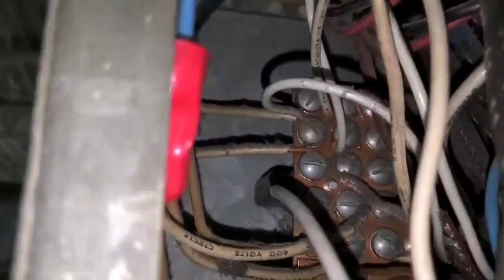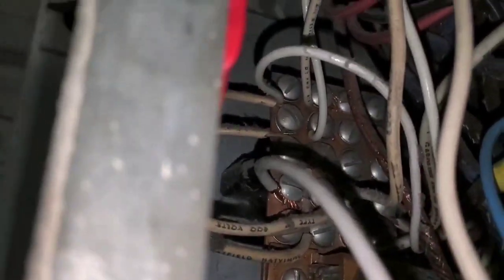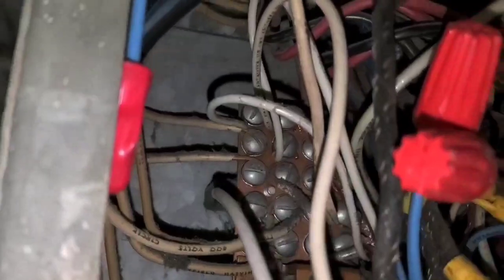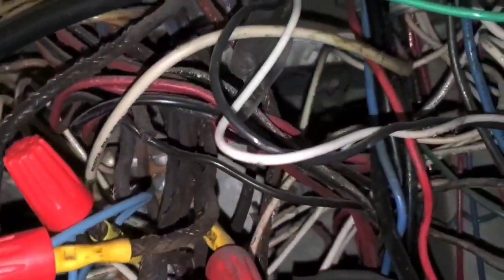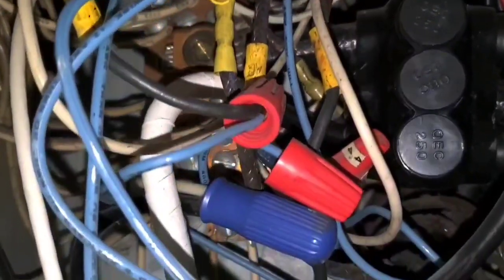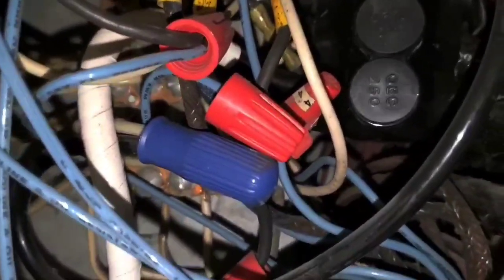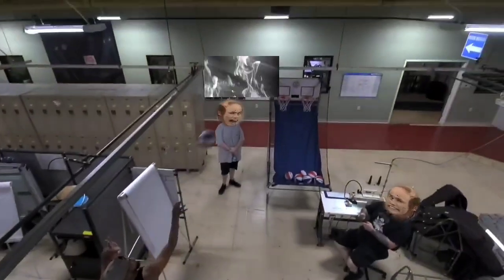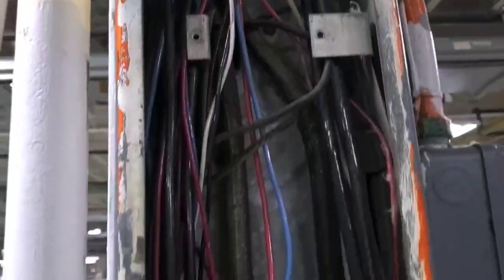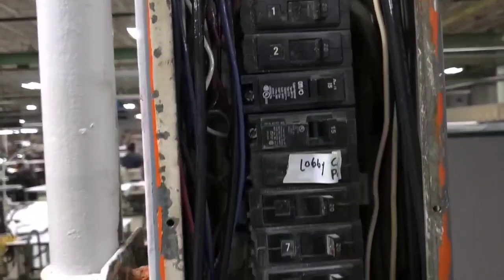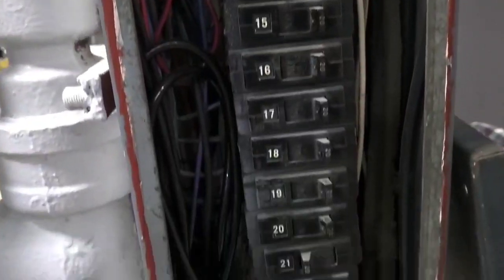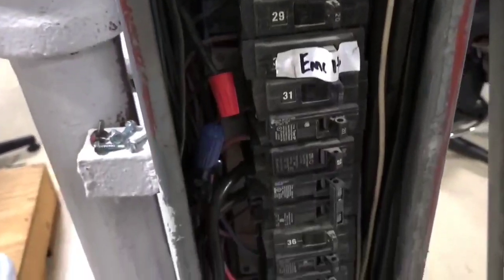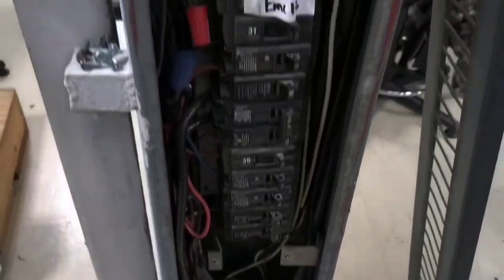Look at this sketchy shit, man. Look at that. There's the neutral bar right there. You need to see up at the top right corner of it. That's where we gotta hook up our neutrals. All behind all that cloth. You have no choice, it's in your contract. Like in 1965, they didn't run the neutral bar in the sub panel. Only the hots are down here. Yeah, they did that.